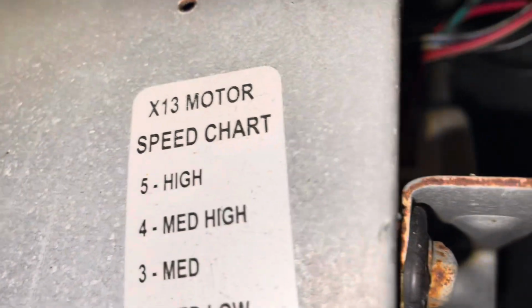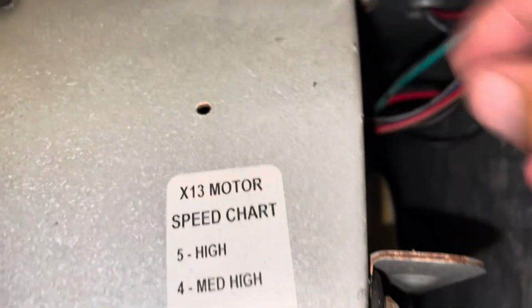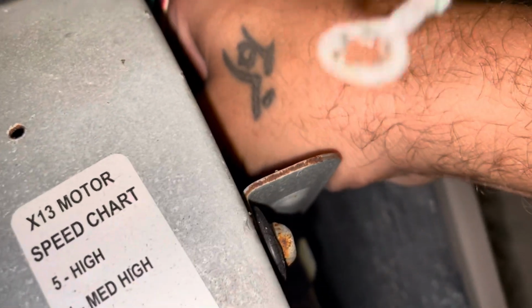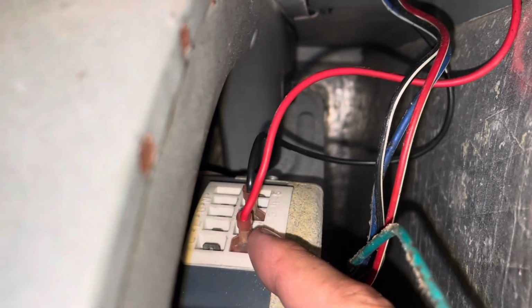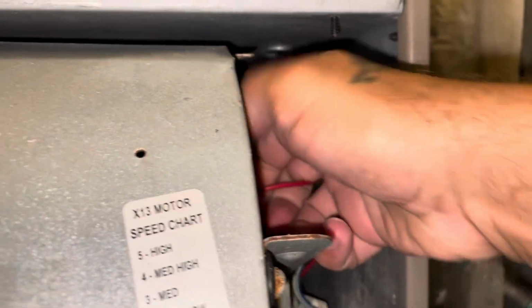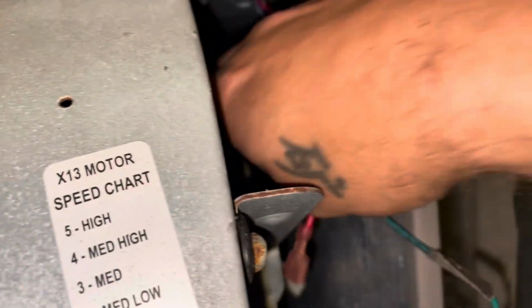I'm gonna pull it out a little bit to get to the wiring here. So basically we have a plug here for our high voltage and our common, we pull that right off. And then these are our speed taps, so we're hooked up to 1 and 3 here, and our motor is loose.